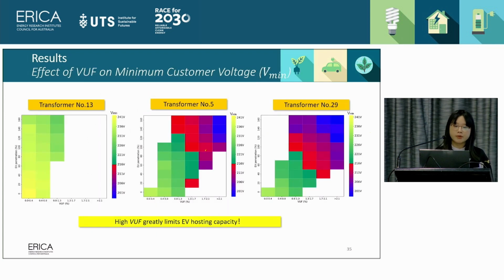So when we analyze the EV hosting capacity, we choose different transformers with different unbalance levels. For transformer number 13, which has a relatively small unbalance level, the maximum unbalance level is 1.3%. Number 5 has a very large one. Number 29 has even larger unbalance. So let's have a look at transformer number 5.